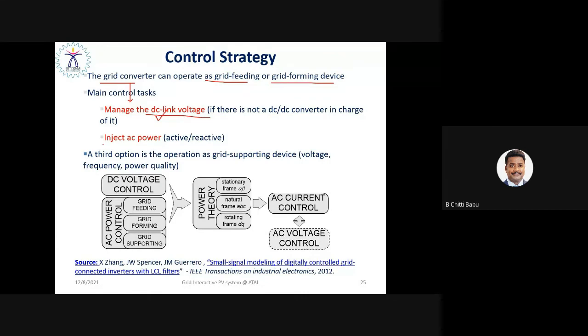In addition to that, it injects controllable AC power, in terms of active and reactive power. As I mentioned earlier, active power control is essential to maintain the frequency constant. Reactive power control is essential to keep the voltage profile at PCC constant. The third option may be a grid supporting device, in terms of voltage, frequency, and power quality, which is called auxiliary requirements. As you can say, the inverter input control is basically a DC voltage control. Inverter output control is basically AC current control and AC voltage control.